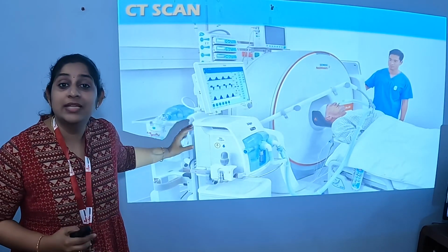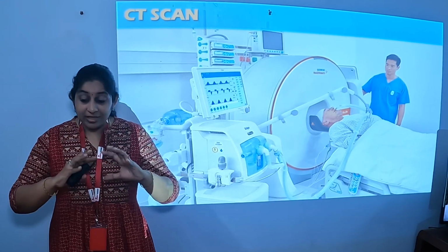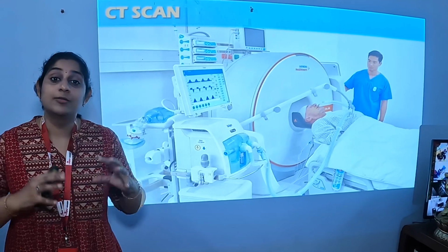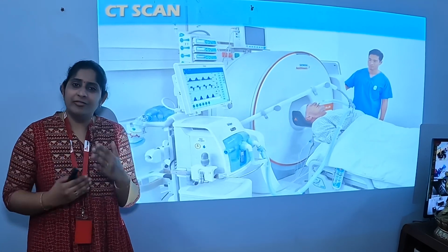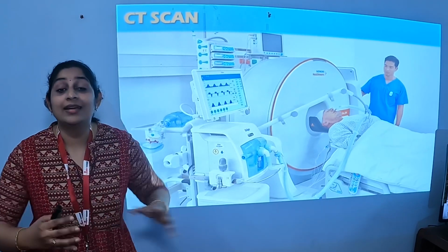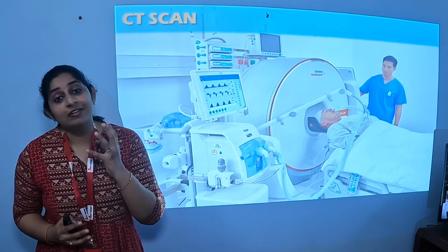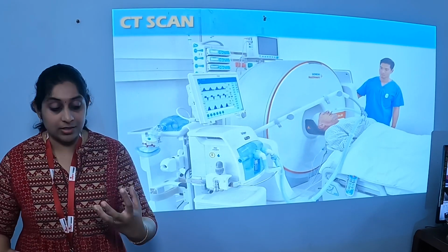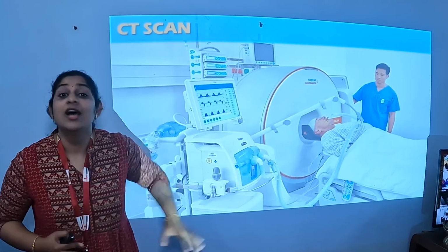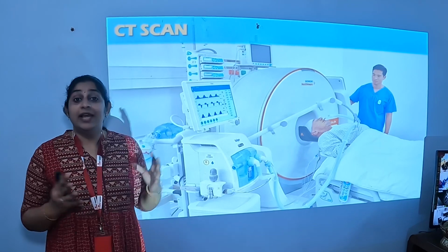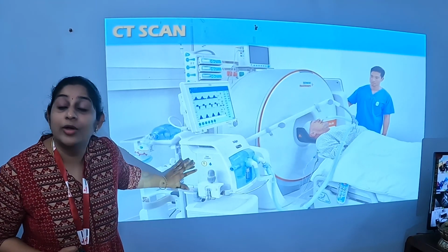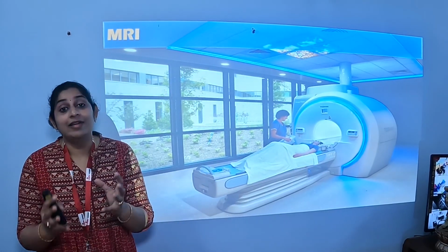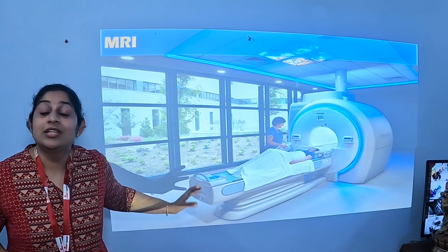When you're going to incorporate a CT machine or the MRI machine, even while building the structure itself, it is better to incorporate a consultant so that it is built in accordance with the AERB norms. There are various machines with various capacities and categories in the CT and the MRI. You have to invest according to your vision and what the consultants are going to give you in terms of cases for your CT or MRI machine. The investment for a CT machine is going to be high, around 2 to 2.5 crores, and when you invest in an MRI, the investment you need to have ready is around 7 to 7.5 crores.